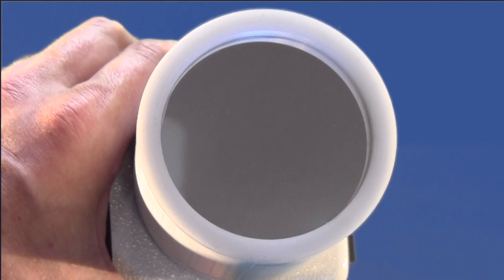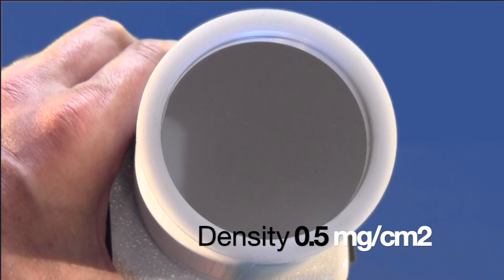For gamma x-ray survey, we keep the beta shield on. If we remove the beta shield, we see a thin mylar window, which is 2 inches in diameter and 0.5 milligrams per centimeter squared in density. It's very fragile, so be careful.